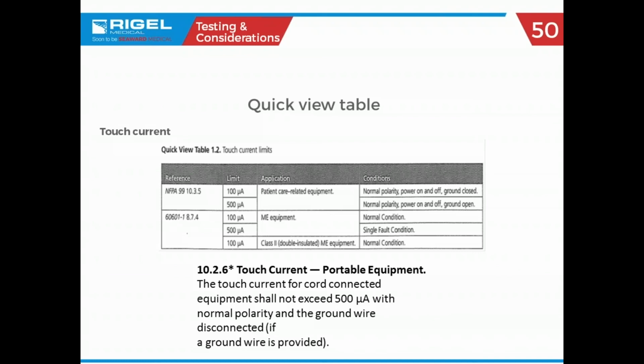So our limits, 100 microamps, 500 microamps. I guess I could just use the pointer rather than blocking part of the screen. 60601, 100 microamps, 500 microamps, 100 microamps, until we get to cardiac floating. And they only want to see 10 microamps. But if you have a 10 lead device, 10 microamps times 10 leads, 100 microamps, what are we testing to for pass-fail? We're testing 100 microamps. So it kind of is the same thing.